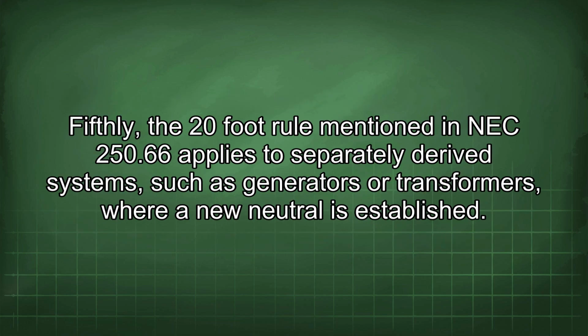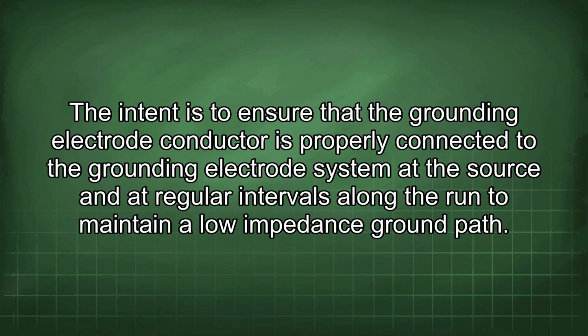Fifthly, the 20-foot rule mentioned in NEC 250.66 applies to separately derived systems such as generators or transformers, where a new neutral is established. The intent is to ensure that the grounding electrode conductor is properly connected to the grounding electrode system at the source and at regular intervals along the run to maintain a low impedance ground path.